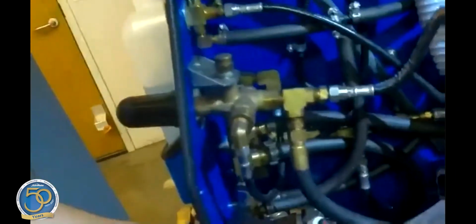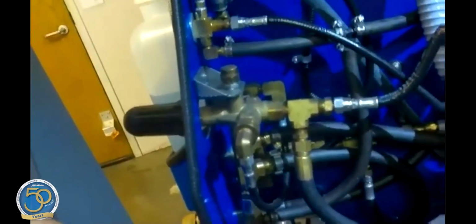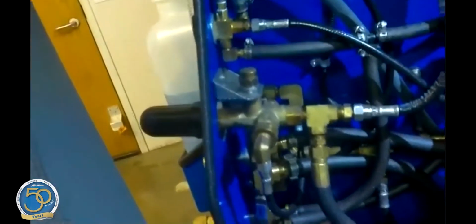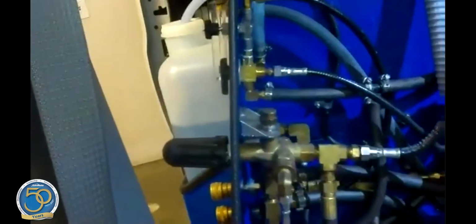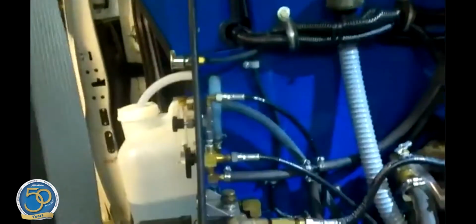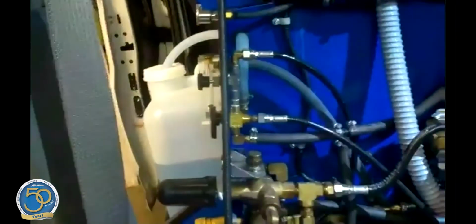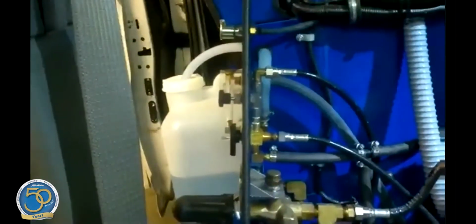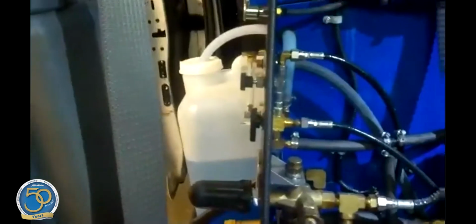So if it's dumping water into your waste tank and it's under 165 degrees—say 140 degrees—then it shouldn't be, and you would need to likely replace that thermal valve. That's the only component as far as the heat management system on the CDS, which is a big reason why I really like the CDS: it's one less system that you really have to service all the time. Simplicity, very much so—yeah, it's very simple.